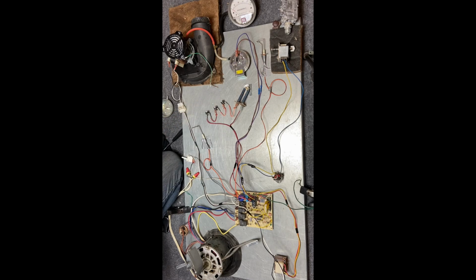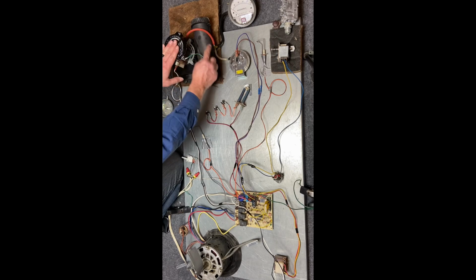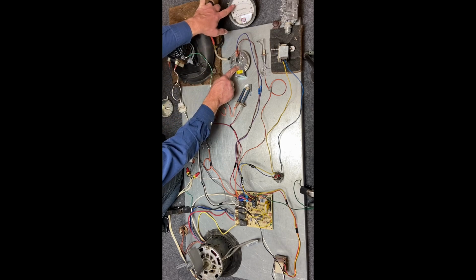So what we're going to do is energize this unit and have it run and go through most of the sequence. Now, since I don't have a flame, it's going to stop at this point and go back through its safeties. But once this motor starts running, it's going to be a little bit loud and it may be difficult to hear. We're going to see this motor run, pull a vacuum here. We're going to see how much pressure we have.